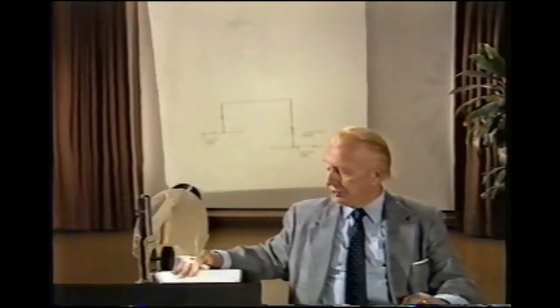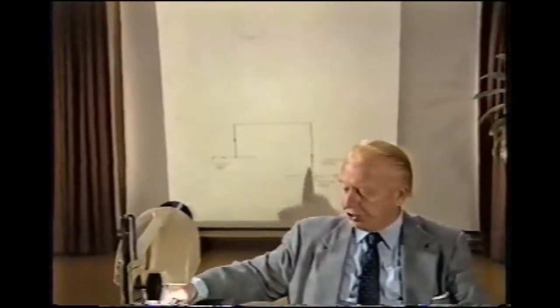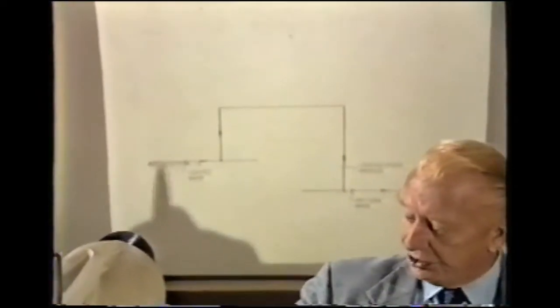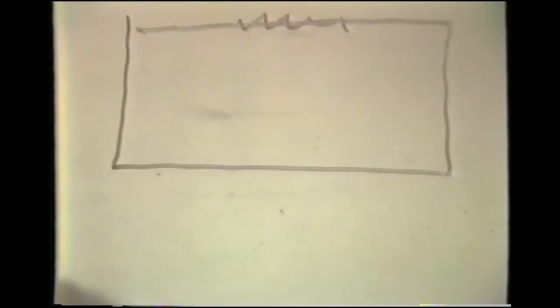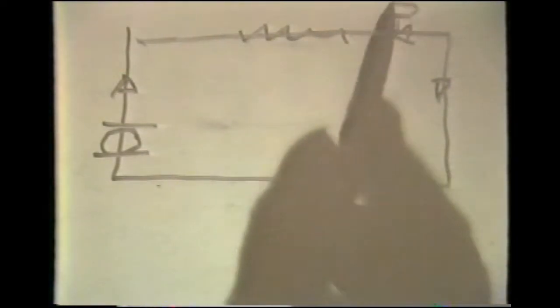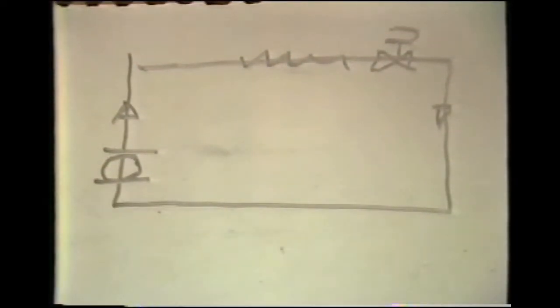This slide again illustrates a crossover bridge interconnected with the primary distribution main. Now, for this illustration, we will have a secondary circuit, which could be a heating comfort area with terminal units, and or it could again be a storage tank as applied, for example, in an industrial area. And we'll have a secondary pump, which is going to pump a constant flow rate through that secondary zone, and or we could apply, of course, two-way control valves to the terminal units associated with that secondary zone.